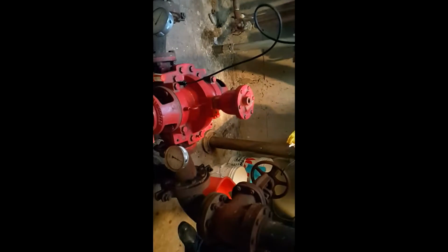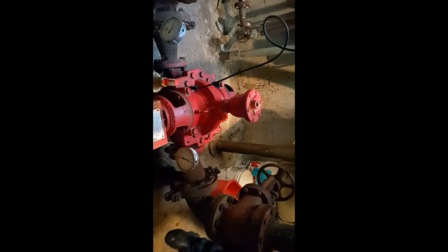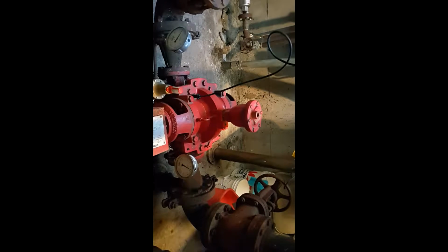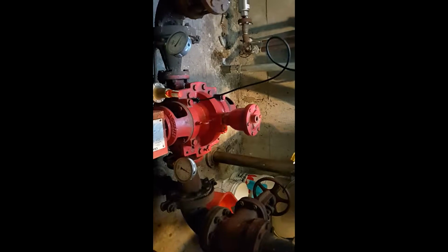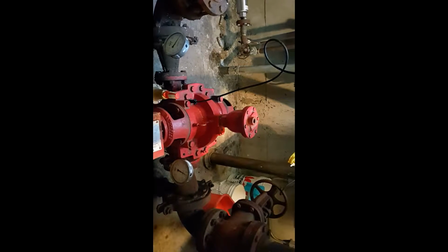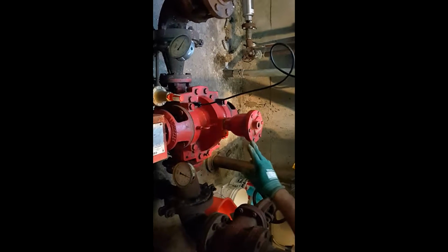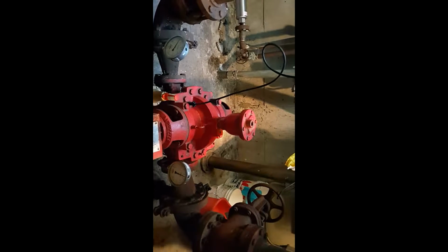Do you know what this thing is by any chance? Yeah, that's your casing relief valve. This pump is a centrifugal pump, so it needs water to move water. It's kind of like sucking through a straw. While you're sucking, the first part you suck is nothing but air. That's what this does. It opens up to relieve all the air, so you get positive suction. That's called your air casing relief valve.